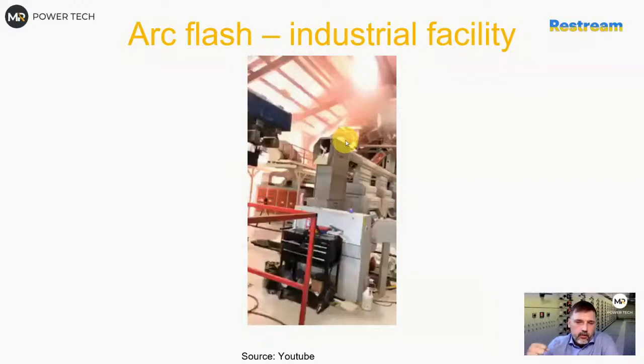The other point is you might have a short circuit current violation. If you just look at the installation in a facility like this, it looks like everything else. On first view, you might find visual issues like this is damaged, this is wrong, this is old, there are no test labels anywhere, so we don't know if it was tested in the last 5 years. You might assume this is in bad shape, but you don't see the internal parts of the breaker, so you can't really know. You have to assume it's not good.